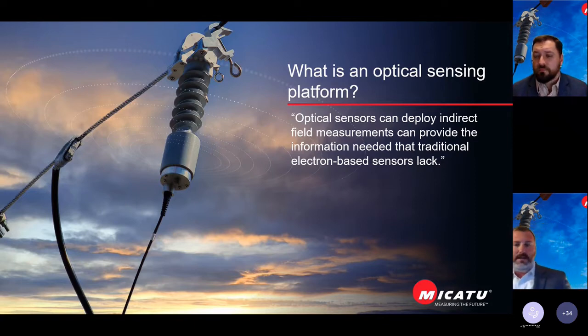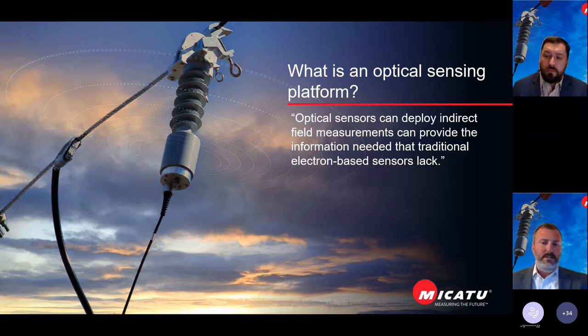Why is it better? That question always comes up. Instead of measuring the grid the old-fashioned way with legacy technologies like a Rogowski coil or legacy CTs and PTs, optical sensing is based on the Pockels effect, which is voltage sensing, and the Faraday effect, which is current sensing. By measuring the intensity of the modulation with a beam of polarized light, you can address and outperform any sensor on the market.